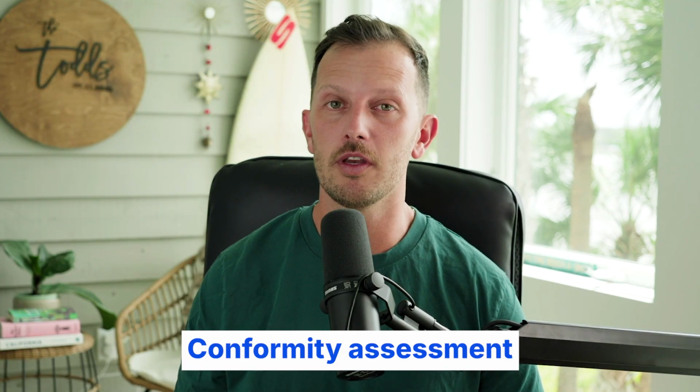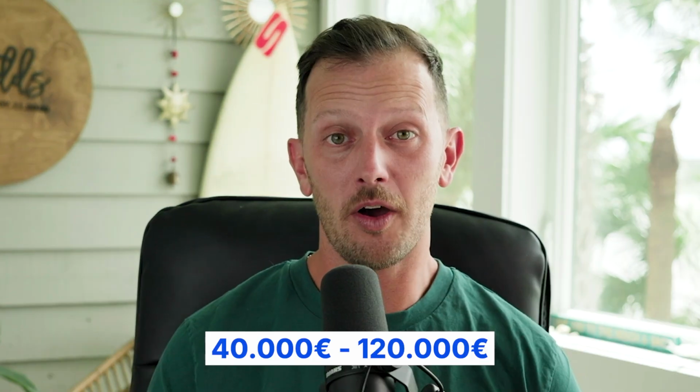Medium and high risk devices require an audit from regulators, called notified bodies in Europe, in order to get their CE mark. Audits are a big deal. This is what I was talking about when I mentioned conformity assessments. Notified bodies do an inspection of your documentation before they can give you a green light for your CE mark. On average, the audit's going to cost you 40 to 120,000 euros, and it'll take up to 6 to 12 months. Class 1 devices, on the other hand, don't require an audit because they're low risk.